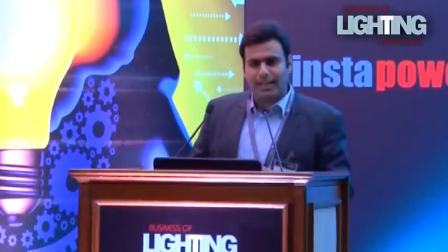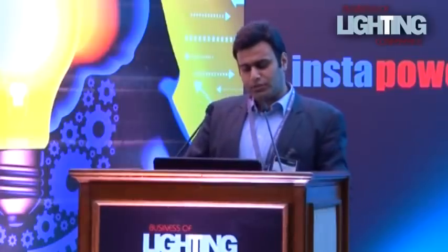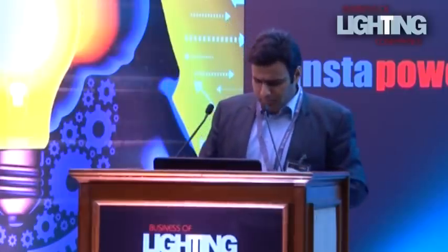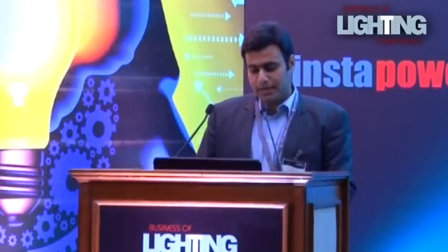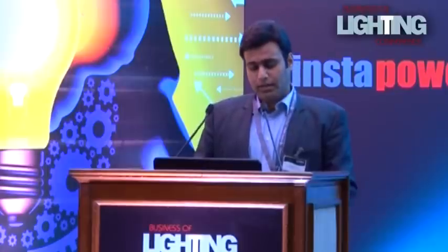Before I integrate the ideal lighting system into my building, it is very essential for me to understand how T8s, T5s, CFLs, LEDs actually behave within the building and how they affect the overall energy load. So I have a 10,000 square feet building here which has a very conventional lighting design, which was done a decade back. One T8 on every workstation. So when I have a fluorescent system, two 26 watt T8s, I have 45 fixtures in all, with an LPD of 25.82, which is huge. Further, if I see the energy consumption of my building here, very high.